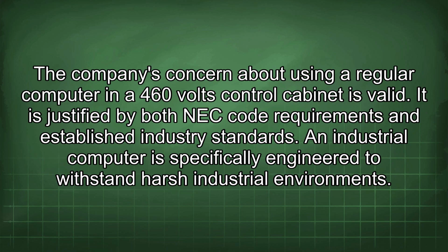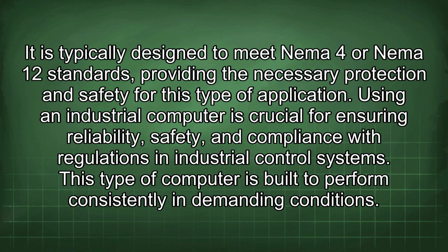The company's concern about using a regular computer in a 460 volts control cabinet is valid. It is justified by both NEC code requirements and established industry standards. An industrial computer is specifically engineered to withstand harsh industrial environments. It is typically designed to meet NEMA 4 or NEMA 12 standards, providing the necessary protection and safety for this type of application. Using an industrial computer is crucial for ensuring reliability, safety, and compliance with regulations in industrial control systems. This type of computer is built to perform consistently in demanding conditions.